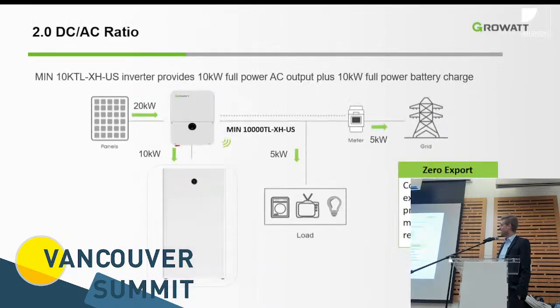There are multiple methods how you can use it. As I mentioned earlier here, you can use a very, very high oversizing. For example, if up to 20 kilowatts of DC power goes to the inverter, 10 can go all the way to the battery, and 10 kilowatts can go into or out of the inverter. In this case, we have an example for 5 kilowatts going to the loads that are currently drawing power, and the excess power, 10 minus 5, in this case also 5, will go to the grid, and you can get your credits or your net billing credits.